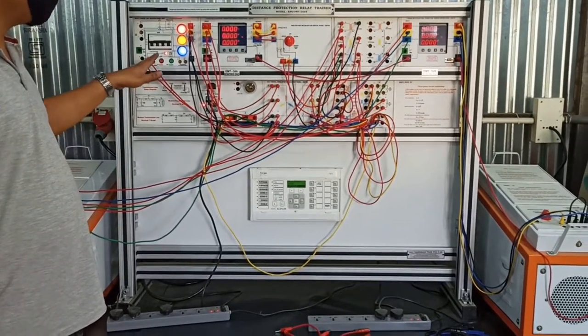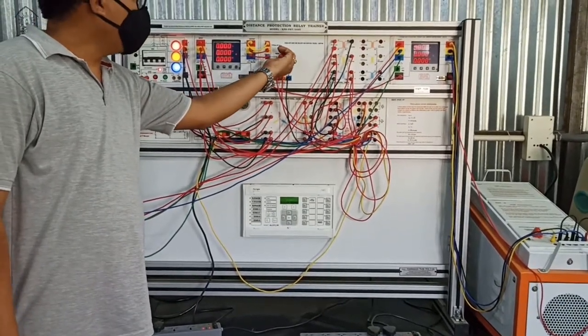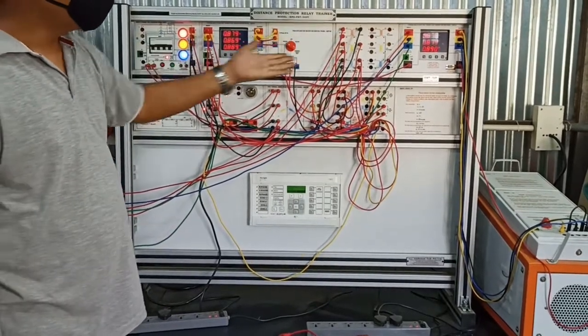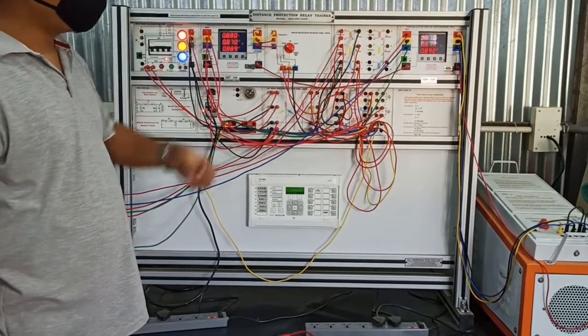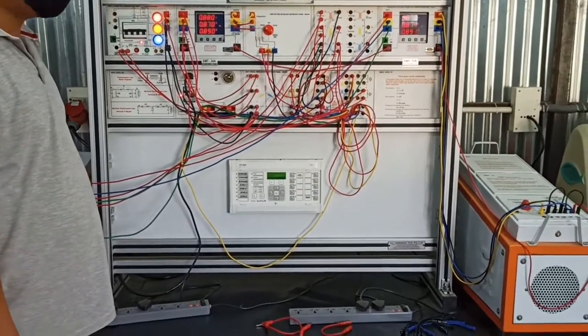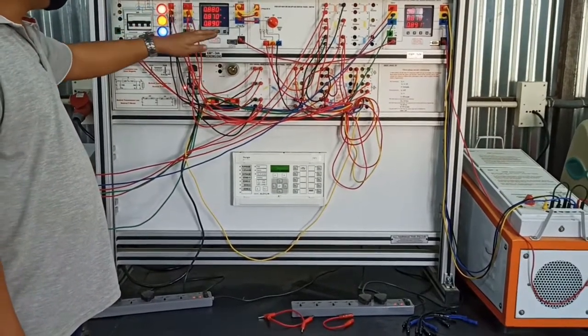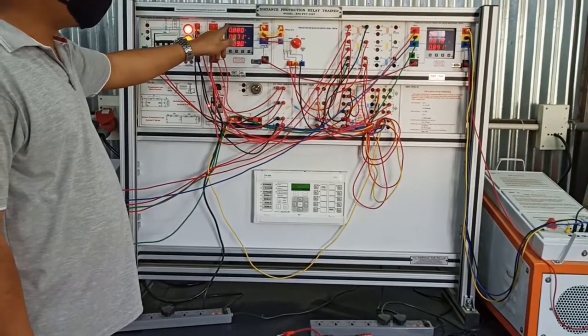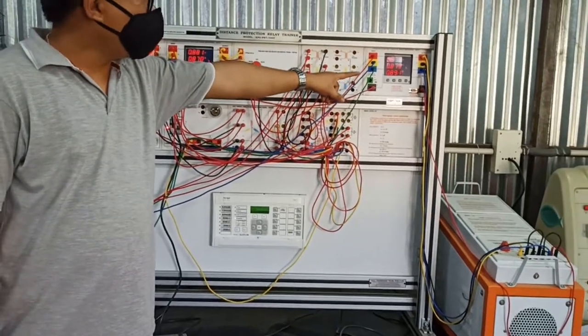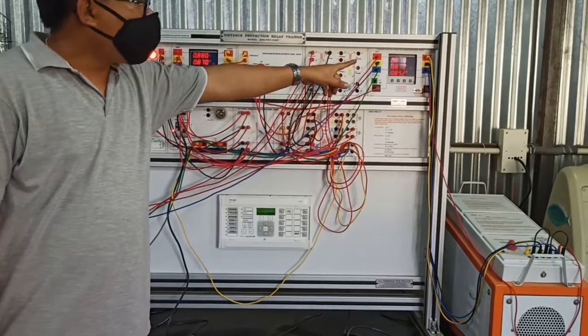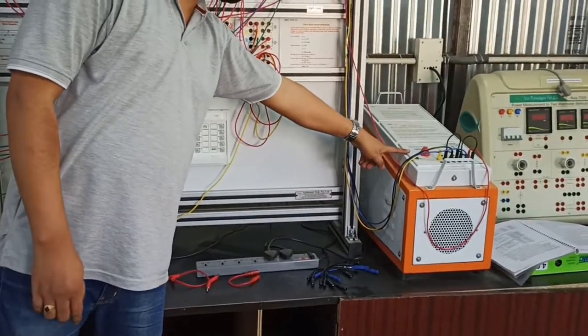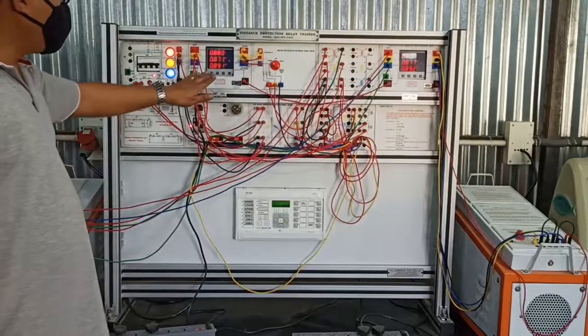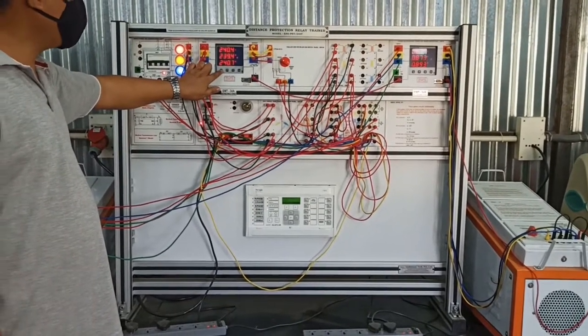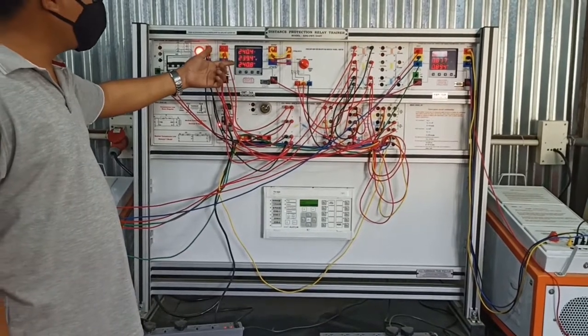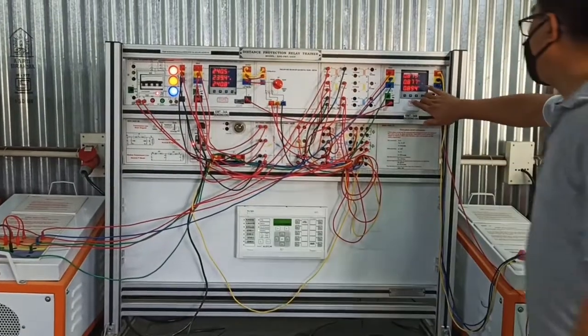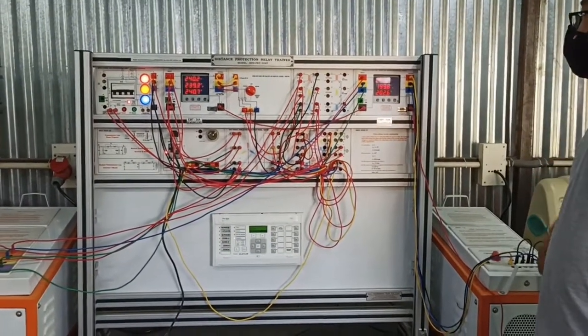When we push the start button and turn this to forward, the two meters EMT34A and EMT34B, the three-phase multifunction power cum energy meters, will show current. It will show 0.8 ampere for all three phases, and on the receiving side also it will show 0.8 ampere. For this one we have to set the position at 225 ohm. Then we can see the line to neutral voltage, which will show around 240, and on the other side it will show around 200.